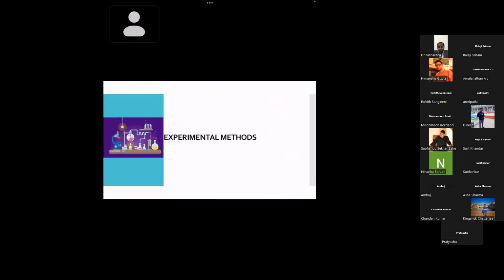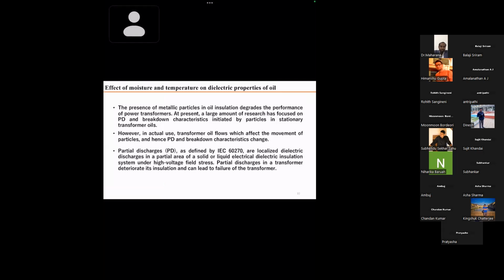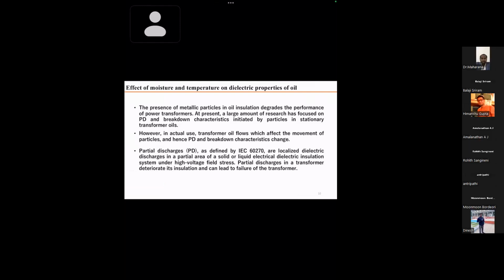So as we got the motivation of how moisture is the villain here, we need to work out how much problem it will create when there is moisture in the transformer oil, and what the maximum limit is. So, the effect of moisture and temperature on the dielectric properties of the oil, because we took these two parameters, or you can consider these two variables: one is moisture and another one is temperature. Both are dangerous for a transformer.